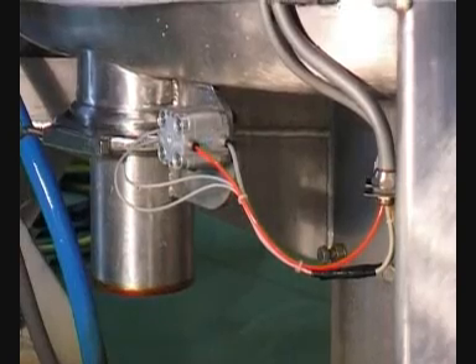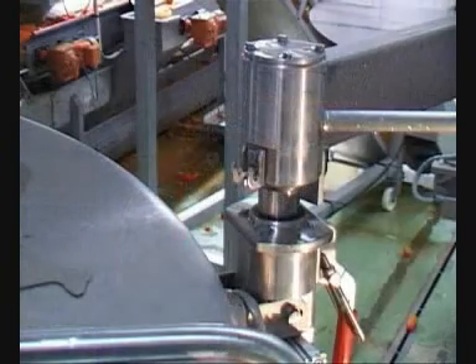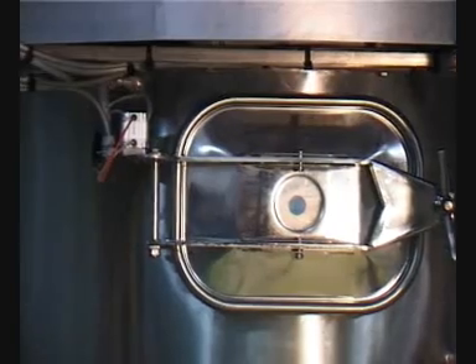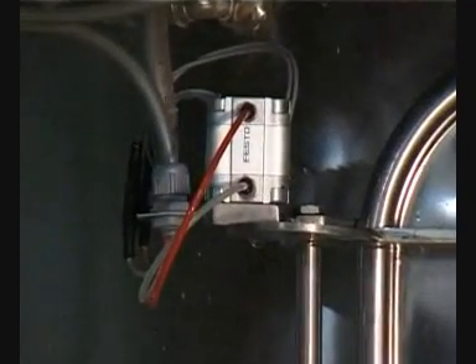With respect to safeties, authorization to open the lid and inspection doors is linked directly to zero speed of the basket. Sorting authorization is dependent on all access panels and doors being safety interlocked.